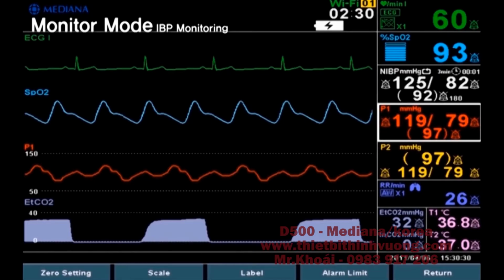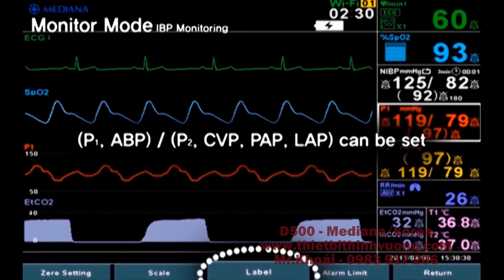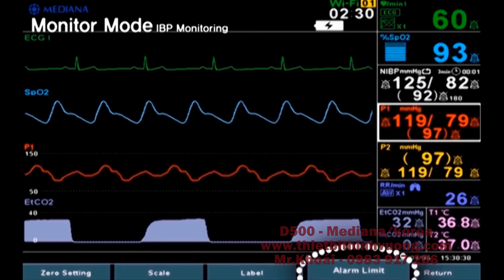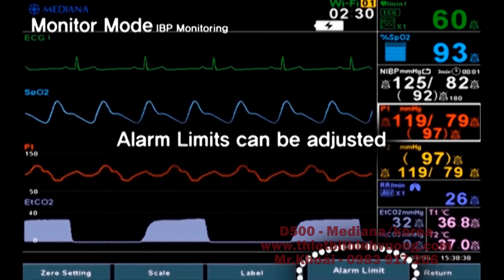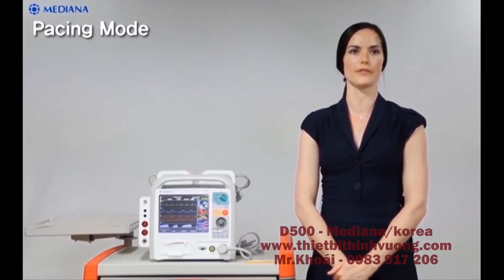Number 3. Label set. P1, ABP, P2, CVP, PAP, LAP can be set. Number 4. Alarm limit. Alarm limits can be adjusted. Pacing mode. The pacing mode is used to deliver a pacing pulse to the heart. Pacing pulses are delivered through multifunctional pads that are applied to the patient's bare chest. The D500 can deliver pacing pulses in either sync mode or async mode.